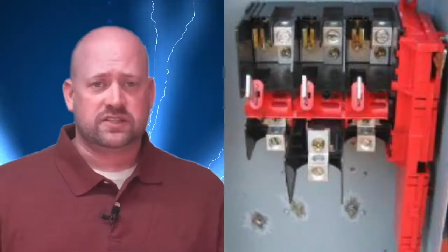So this can all be prevented by installing an appropriately sized SPD, or surge protective device. These are the items formerly known as a TVSS, or transient voltage surge suppressor. Now, installing the proper SPD is the most cost-effective means of improving your client's power quality, doubling or tripling the life of their electrical and electronic equipment, and helping their bulbs last 4 to 6 times longer.